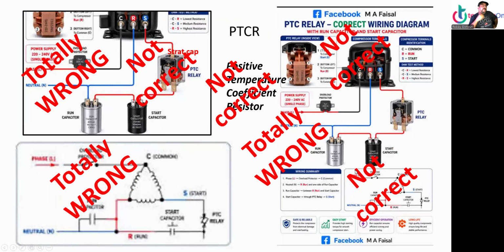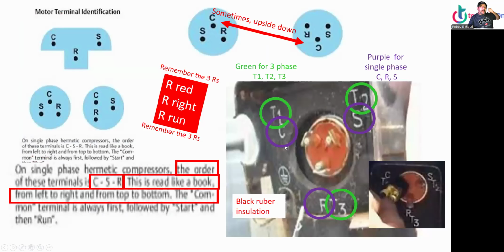Alrighty. So a lot of things are totally wrong online. Look at this idiot, he somehow has the run capacitor and start capacitor together. Look at that. Alrighty. Don't believe everything you see. And this is from the book, and it's also wrong. From the book: on single phase compressors, the order of the terminals is CSR. That's not true.